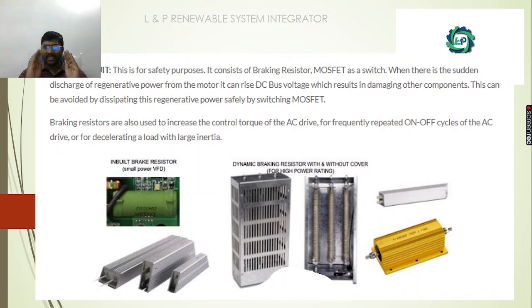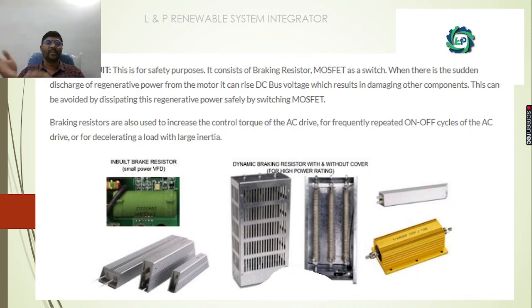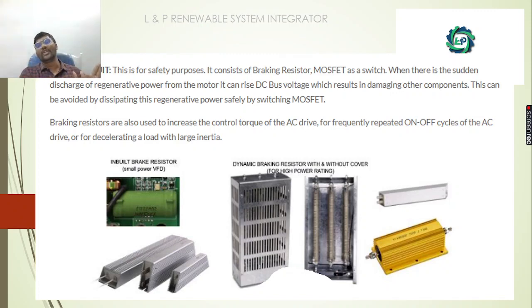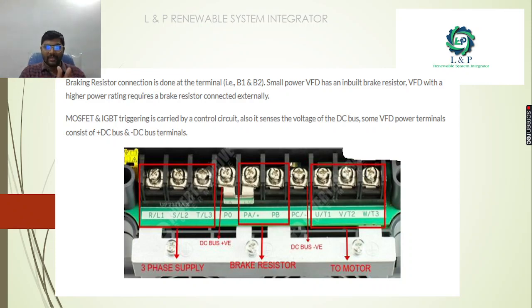The brake circuit — its main use is for safety purposes. Nowadays, in most advanced VFDs, we have inbuilt brake circuits. That is nothing but braking resistors, or sometimes MOSFETs used as a switch in the brake circuit. But for high voltage variable frequency drives, we need to separately provide the braking resistors and the MOSFETs as switches. This braking resistor has the following terminals: positive and negative terminals, often referred to as B1 or B2, or PA+ or PB-.